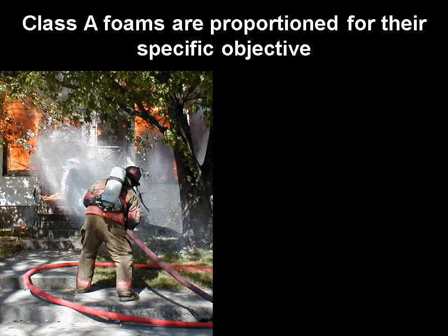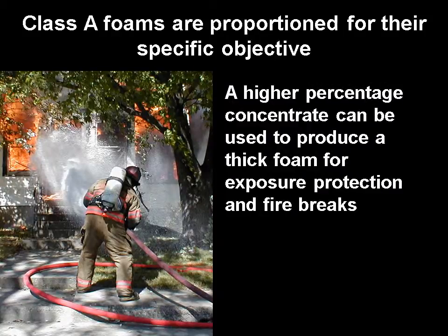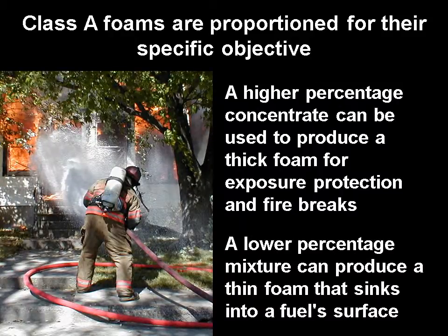Class A foams are proportioned for their specific objective. A higher percentage concentrate can be used to produce a thick foam for exposure protection and fire breaks. A lower percentage mixture can produce a thin foam that sinks into fuel surfaces. So it depends on what your assignment is to do.